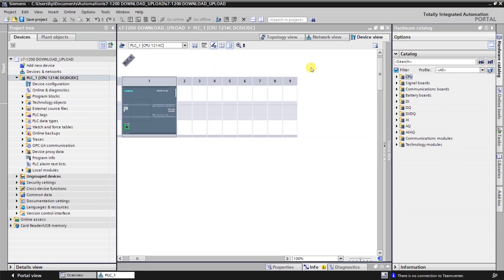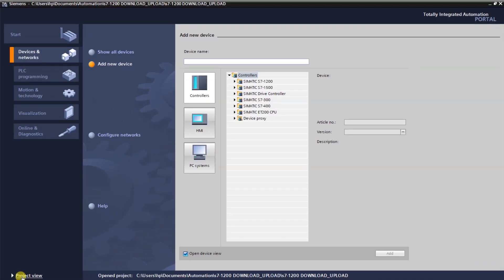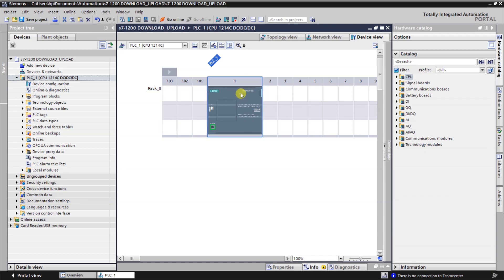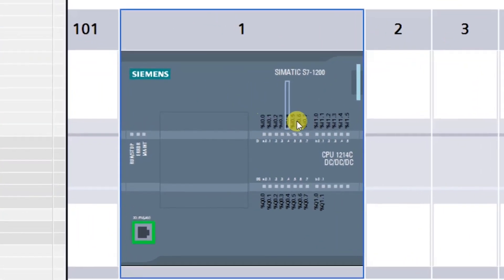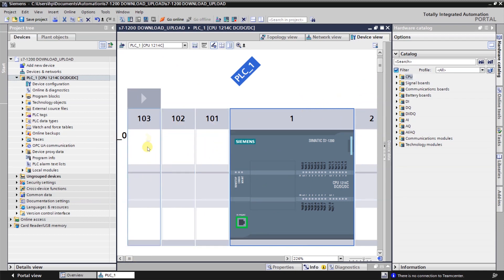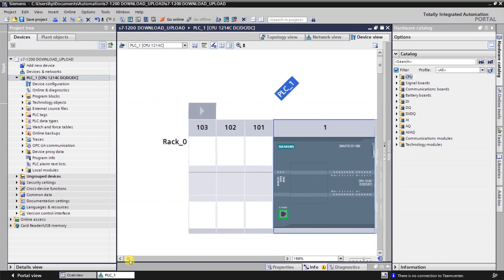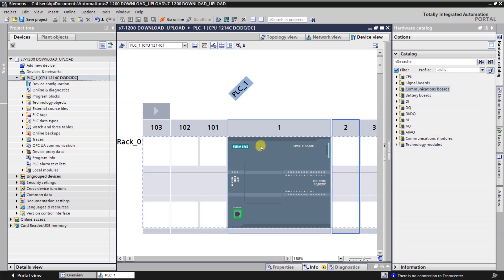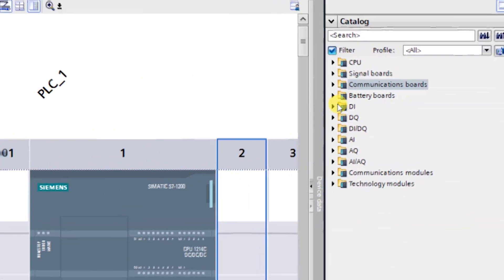A new screen appears — the project view. You can switch between portal view and project view from the bottom left. In the project view, the S7 1200 PLC has been added. You can zoom in to see 14 digital inputs and 10 digital outputs. We can add up to eight signal modules on the right, three communication modules on the left, and one signal board to the PLC.